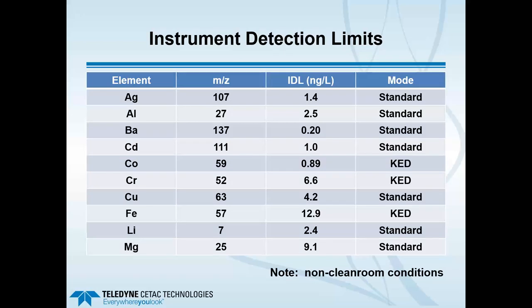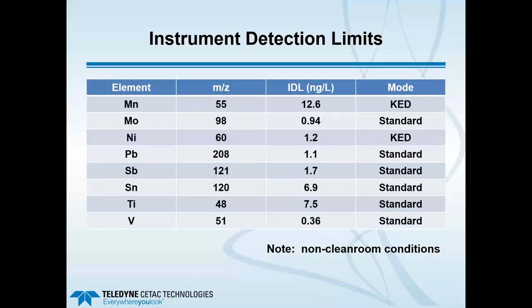Instrument detection limits ranged from about 0.2 to 15 nanograms per liter, or 0.2 to 15 parts per trillion. You can see the elements done in standard mode (no KED gas) and some run with KED, including cobalt, chromium, and iron. This analysis was done under non-cleanroom conditions and without an electronic grade of isopropyl alcohol — we did not have electronic-grade IPA available for these tests. So these detection limits are quite good considering the conditions.